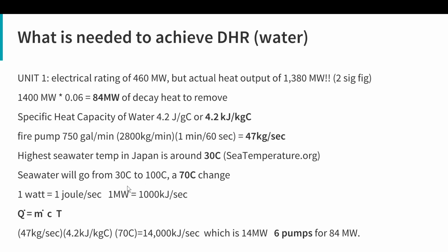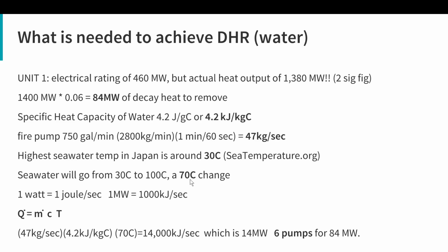We're going to assume that the seawater on the secondary side is going to go from 30 Celsius to 100 Celsius. Of course, it's going to take more energy for that to then become steam, if it's like an evaporative condenser or whatever. But we're just going to use the energy from 30 degrees Celsius to 100 degrees Celsius, a 70 degree change. And by definition, 1 watt is 1 joule per second, so 1 megawatt is 1,000 kilojoules per second. And you guys might remember this: heat over time equals mass flow rate over time times the specific heat capacity times the temperature change. So doing these calculations, we end up with 14 megawatts. So that's one fire pump that pumps 750 gallons a minute, pumping water that's going to change 70 degrees Celsius, and it is going to end up removing 14 megawatts of power. So we need 6 pumps, conservatively, probably more like 10 pumps, to make sure that we can remove 84 megawatts.